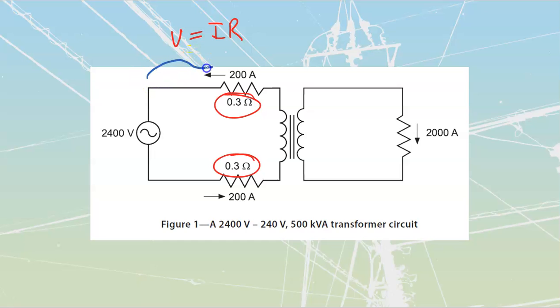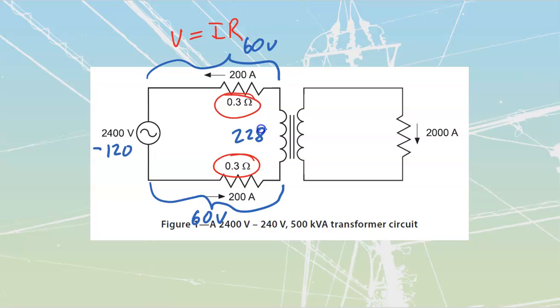So from source all the way over to the transformer, I'm going to be dropping 60 volts on that line, and I'm also going to be dropping another 60 volts on this line. Same resistance, same current going through it, which means 60 volts plus 60 volts is 120 volts. So the 2400 volts we have is actually going to be 2400 minus 120, leading us to a series circuit: 60 volts, 60 volts. What we must have left, according to Kirchhoff's voltage law, is the remainder, which in this case is 2280 volts.